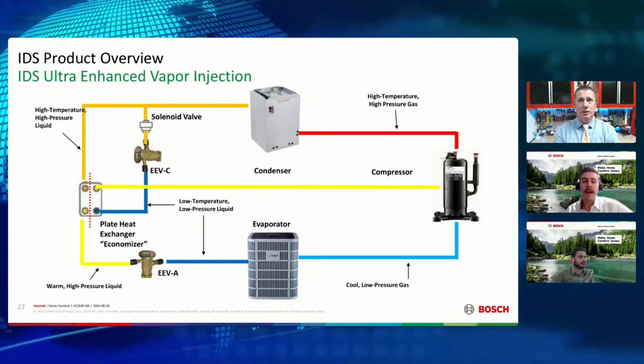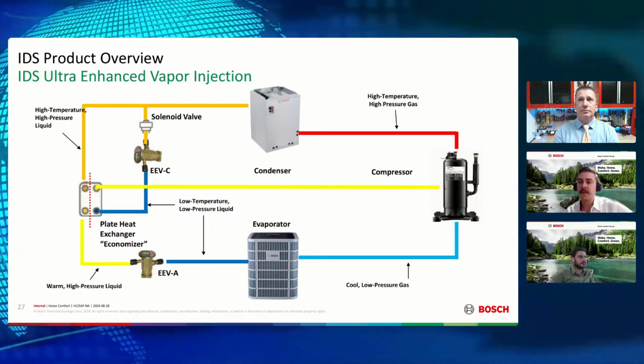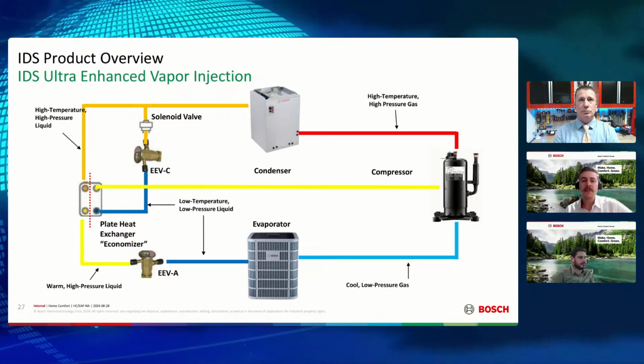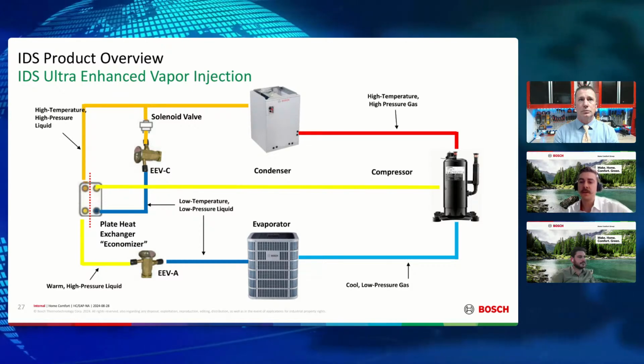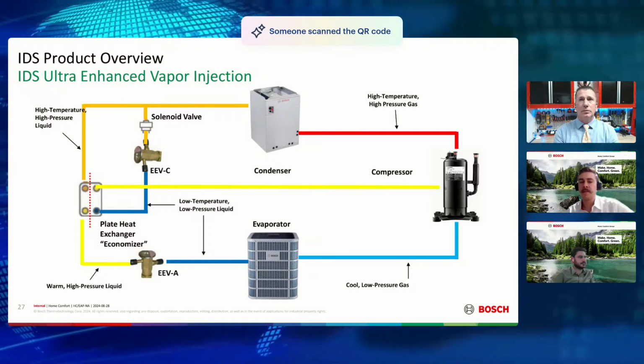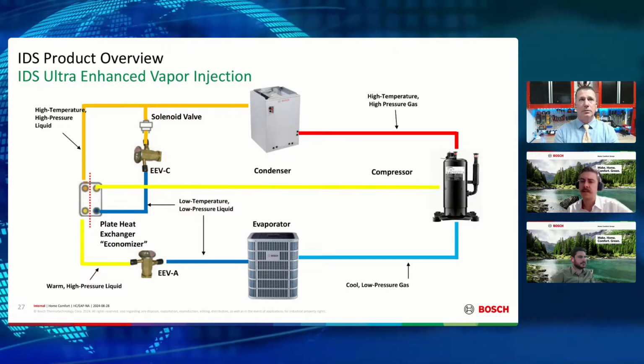And the refrigerant flow would be reversed. So what we're going to do is close that solenoid valve to ensure that no refrigerant is going to go through there. That ensures that we don't have to use all of the capacity cranking down EEVC to close, because those valves are going to have some amount of leakage anyway.